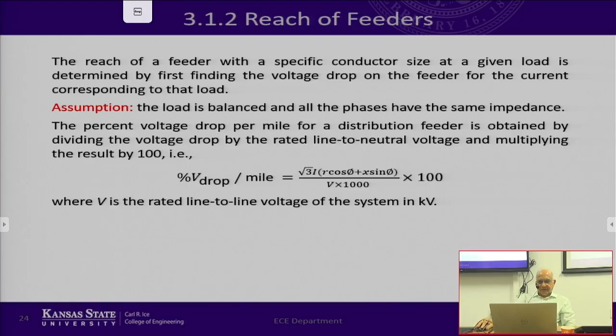Okay, and then we have these line conductor values based on economics, and now we are going to calculate the reach of the conductors. How do we do that? We consider that the allowed voltage drop is delta V. From the substation to the end of the line, what is the voltage drop that is allowed? Now, typically in a distribution system, delta V is 7.5%.